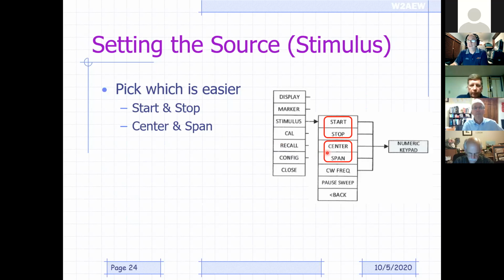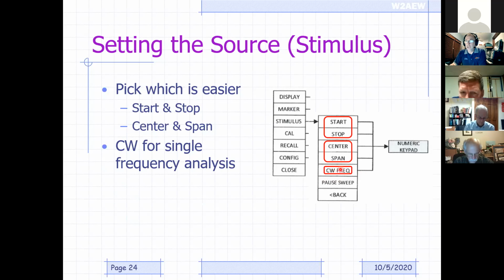Okay, if you're measuring an antenna, sometimes it's easy to set the start and stop. You want to set it at the band edges, for example. But if you're measuring a filter, you might say, I know the center frequency of my filter is supposed to be 455 kilohertz, and I want to measure 100 kilohertz around that. Okay, so that's center and span. So you pick whichever one of those 2 is the most convenient for the situation that you're measuring. And selecting any one of those buttons will bring up a numeric keypad on the display for you to enter the numbers in. There is the ability to set up a CW frequency. So if you only want to measure something at one frequency, you can do that instead of doing a sweep. So that's what the CW frequency is for.